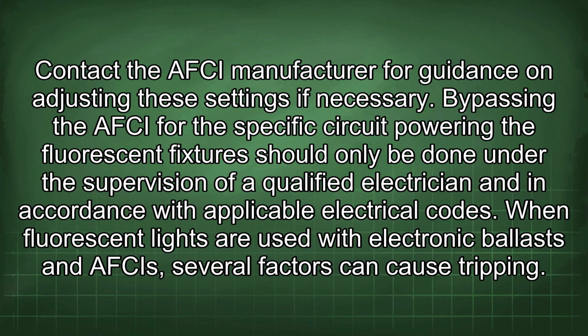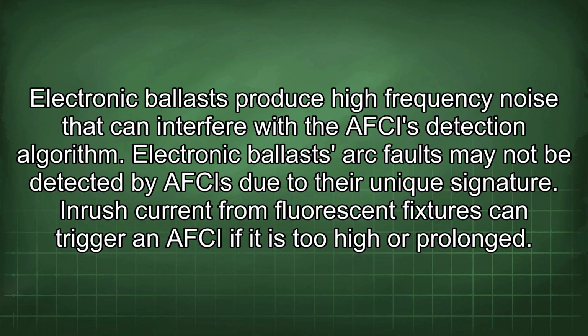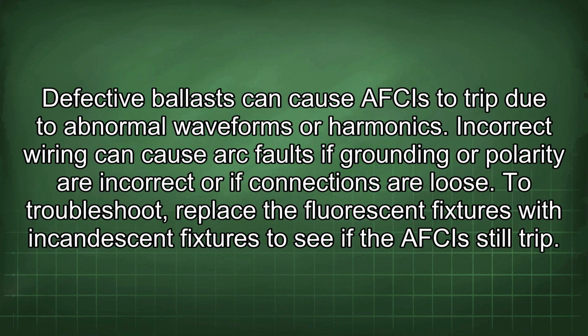When fluorescent lights are used with electronic ballasts and AFCIs, several factors can cause tripping. Electronic ballasts produce high-frequency noise that can interfere with the AFCI's detection algorithm. Electronic ballast arc faults may not be detected by AFCIs due to their unique signature. Inrush current from fluorescent fixtures can trigger an AFCI if it is too high or prolonged. Defective ballasts can cause AFCIs to trip due to abnormal waveforms or harmonics. Incorrect wiring can cause arc faults if grounding or polarity are incorrect or if connections are loose.